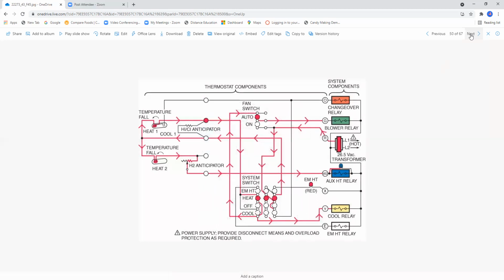Okay, another picture showing how it electrically looks in the heat mode. This is the system switch energized to heating. Notice you've got your anticipators. Notice that as the temperature falls, heat 1 will come on. As the temperature continues to fall, then the second stage will come on. The anticipators are designed basically to prevent overshooting of the thermostat. Today it's done electronically, and they're very accurate, within 1 or 2 degrees. I've never had any issues.